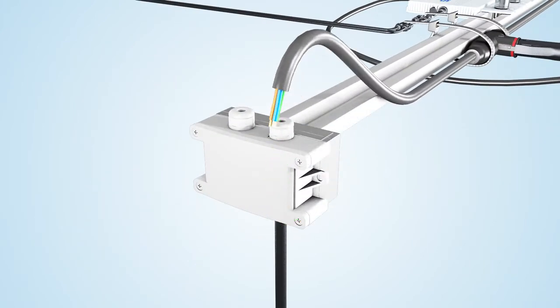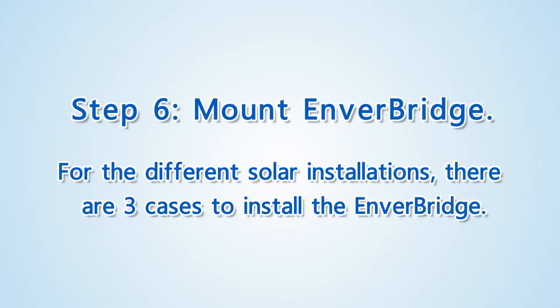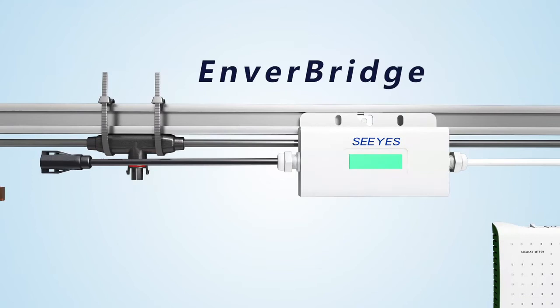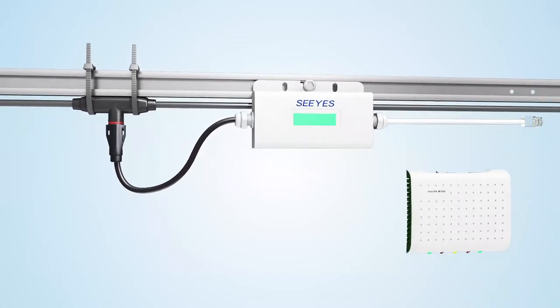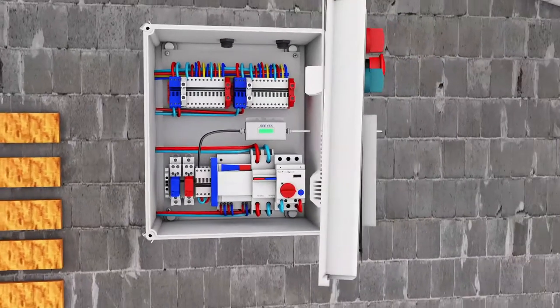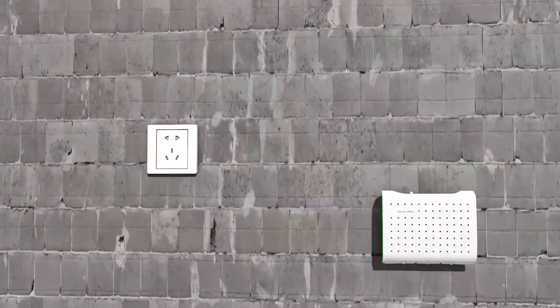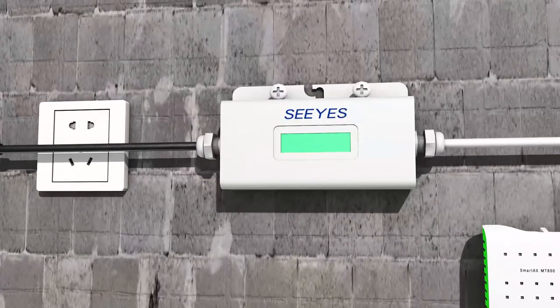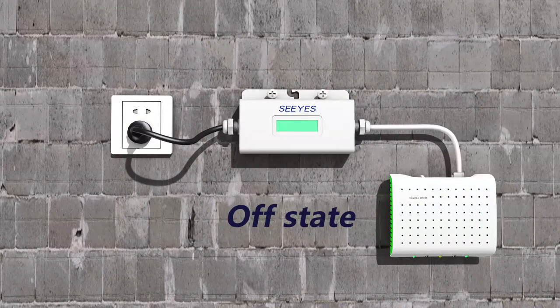Step 5: Connect the trunk cable to the junction box. Step 6: Mount the Enverbridge. For different solar installations, there are three cases. Case 1: Fix the Enverbridge on the rack near the junction box. Case 2: Fix the Enverbridge in the house distribution box. Case 3: Fix the Enverbridge on the wall near the wall plug. Please note that the breaker in the distribution panel for the PV system must be kept off until the whole system is completed.